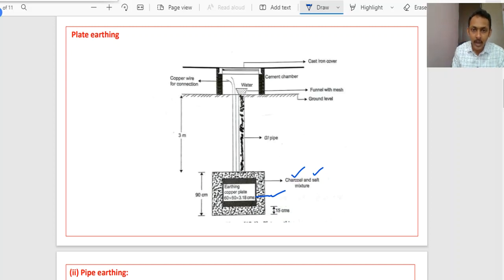Here we have a galvanized iron pipe, and this is the ground level, and we have a cast iron cover. All these arrangements are made at a depth of around 3 meters, nearly 10 to 11 feet. We have to insert this copper plate.